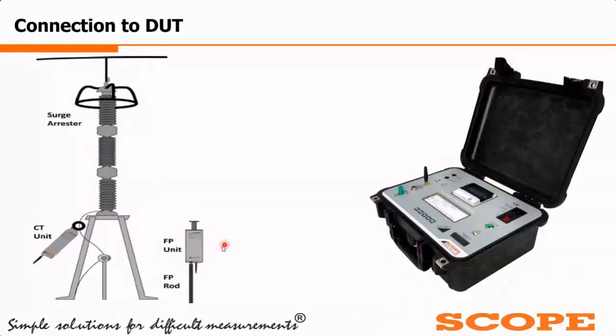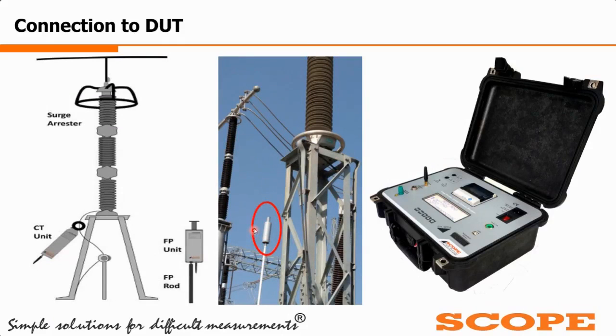Now this CT unit and field probe unit are equipped with wireless sensors, so they measure all the data separately and wirelessly send it to the base unit. As I was telling, this field probe unit must not be taken beyond the base of the LA. You can keep it a little bit lower than the LA base, no problem, but it must not cross the base height. The base level I must not cross at any condition. So this is the instrument, very simple to connect and very simple to operate.